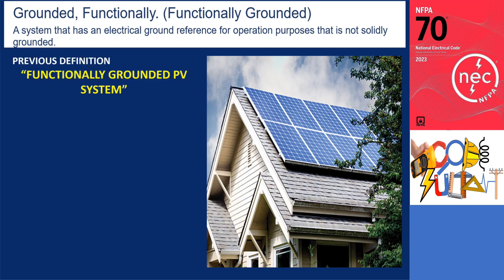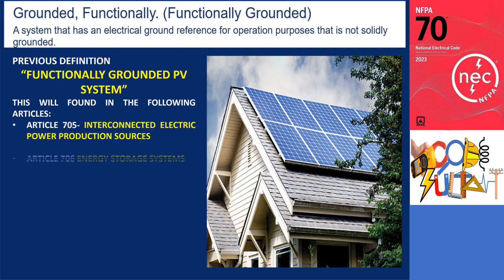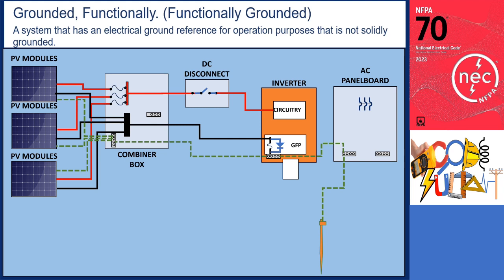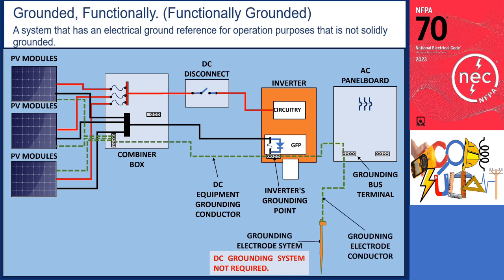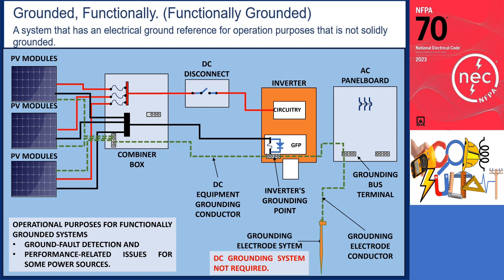The term functionally grounded PV system has been revised to functionally grounded by the format used in Article 100, because the definition is referenced in multiple articles such as Articles 705, 706, and 712. Functionally grounded refers to a system that has an electrical ground reference for operation purposes that is not solidly grounded. The ground connection is established through electronic means internal to an inverter, which also provides ground fault protection. This configuration allows the equipment grounding conductor of the PV circuit to be connected to the inverter's grounding point, eliminating the need for a separate DC grounding system. The inverter's grounding point is then connected to the grounding system or grounding electrode of the residential facility or building. Functionally grounded systems serve various operational purposes such as ground fault detection and addressing performance-related issues for certain power sources.